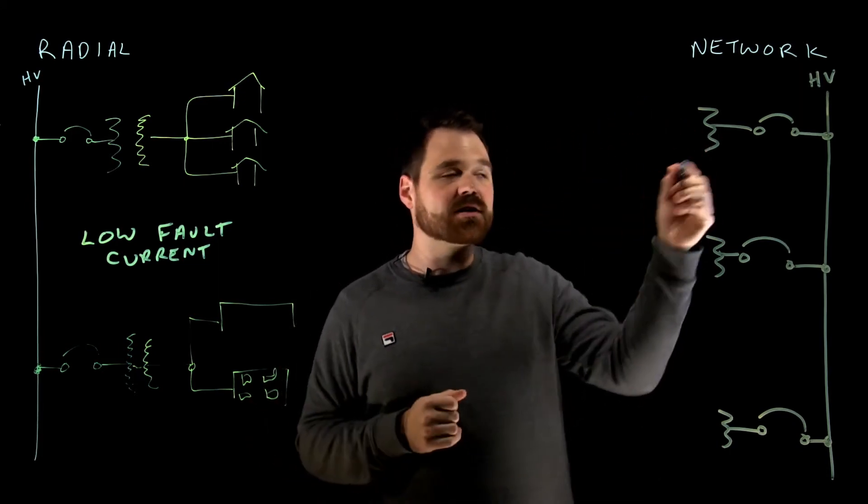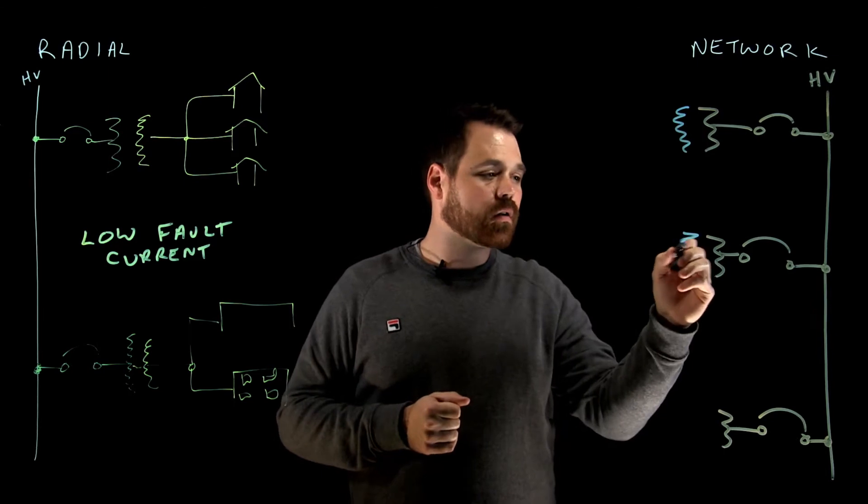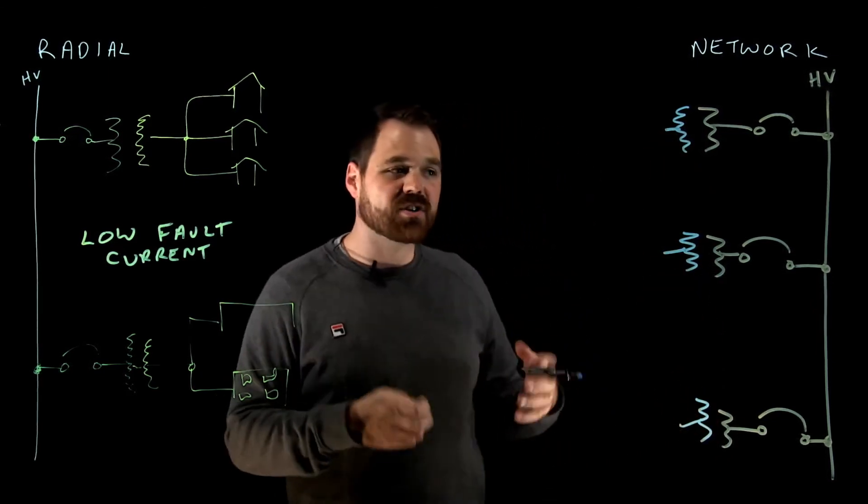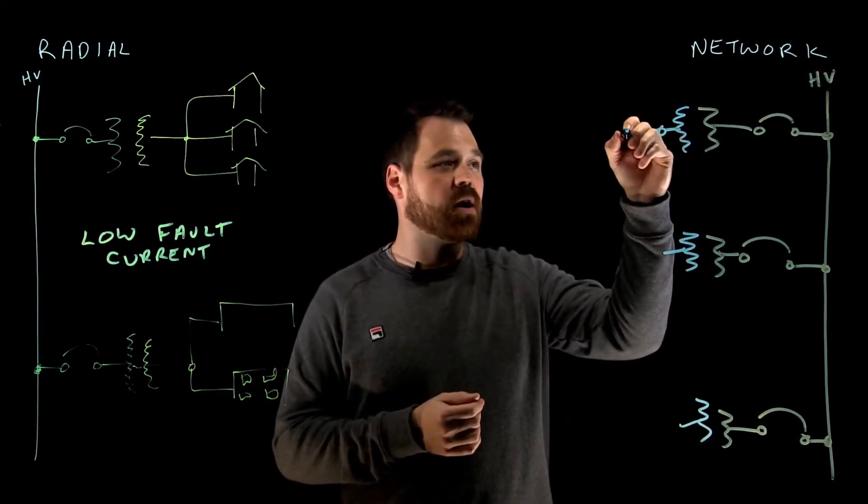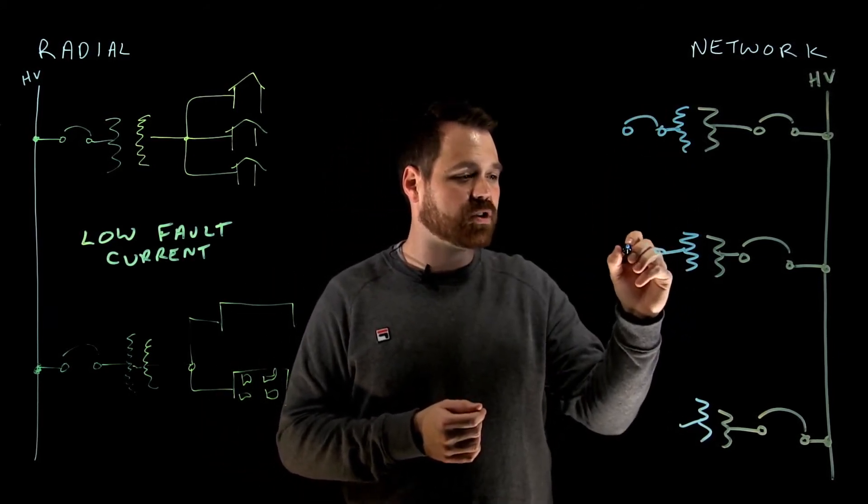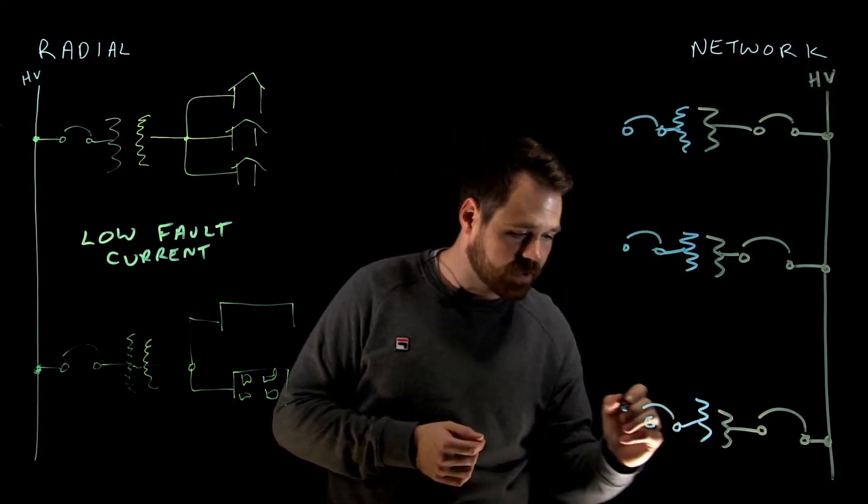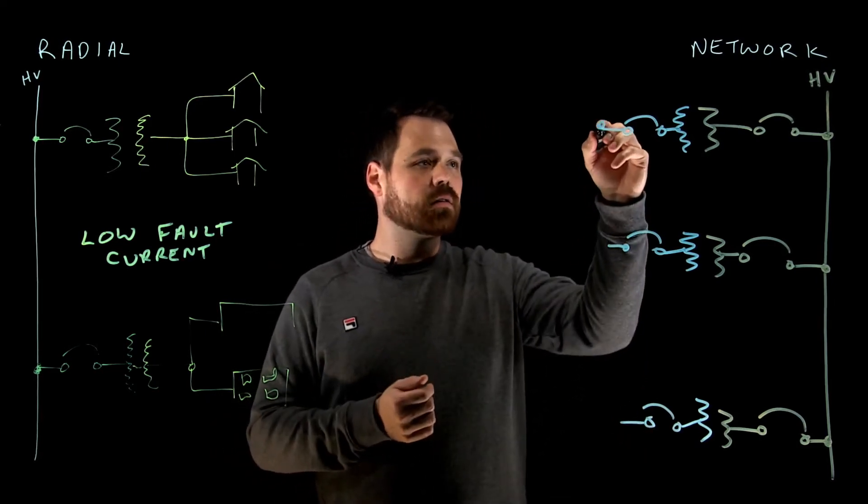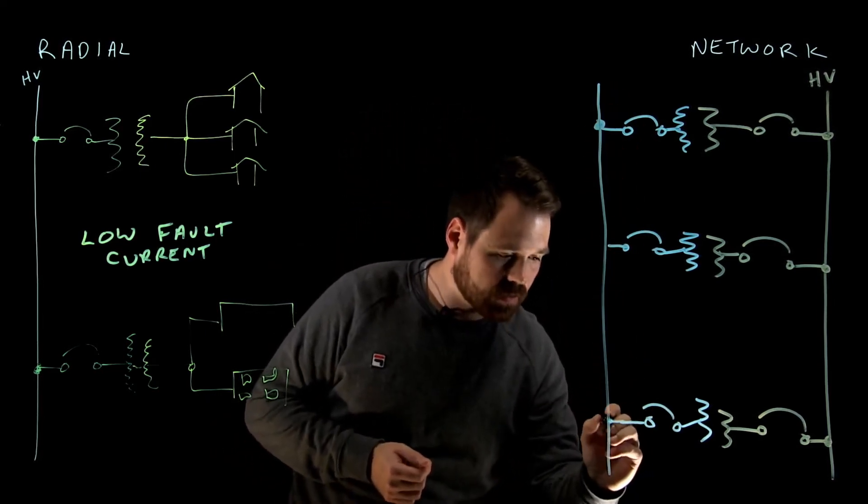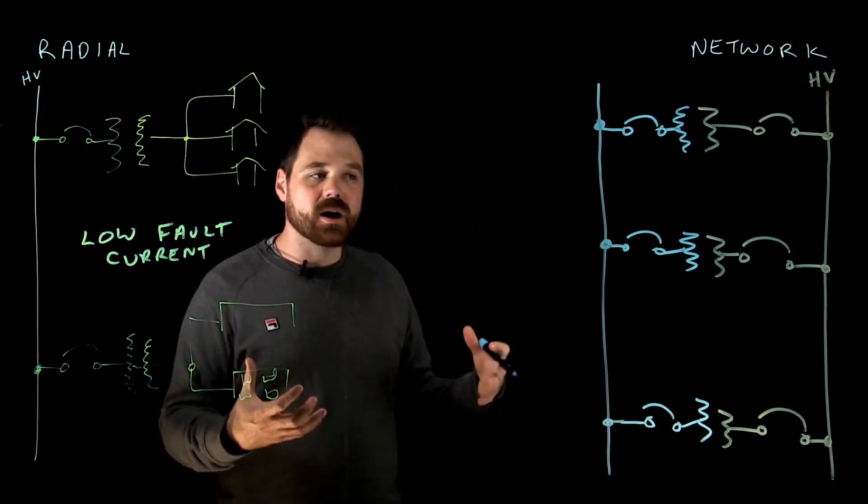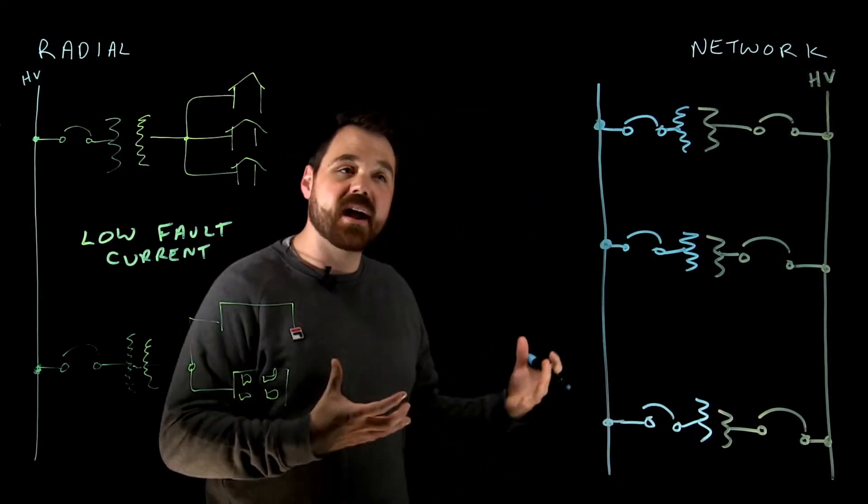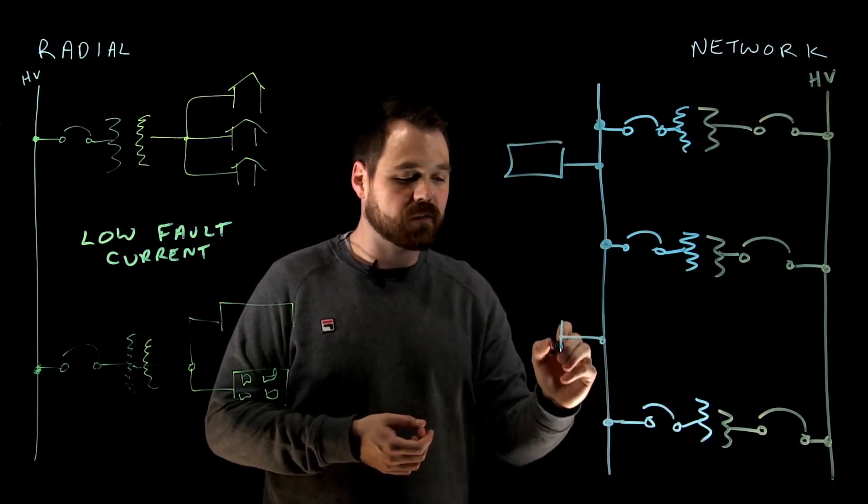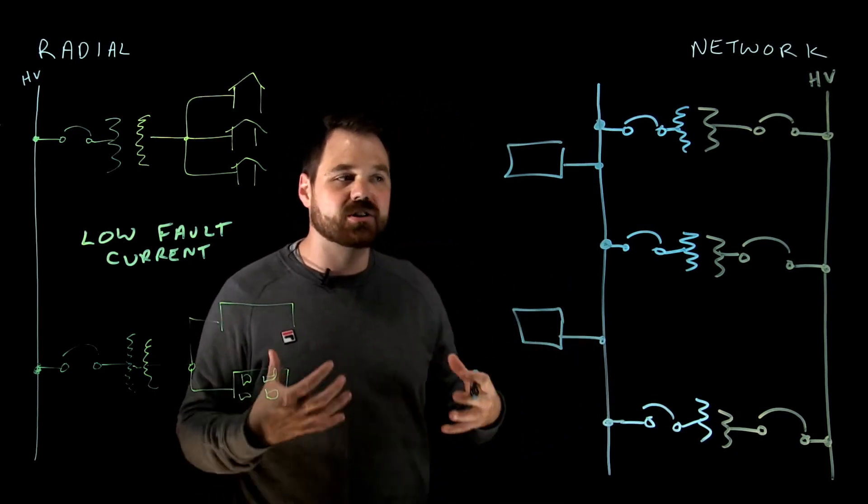Now the difference here comes in the secondaries of these transformers. So in a network system, we also are going to parallel the secondaries of these transformers. Now because of that, we also are going to require that disconnecting means and protection - just using a circuit breaker for simplicity. These are all going to be connected in parallel as well. Then from there, what we would do is we would go feed the loads - go feed that bigger, most likely bigger commercial or institutional loads.